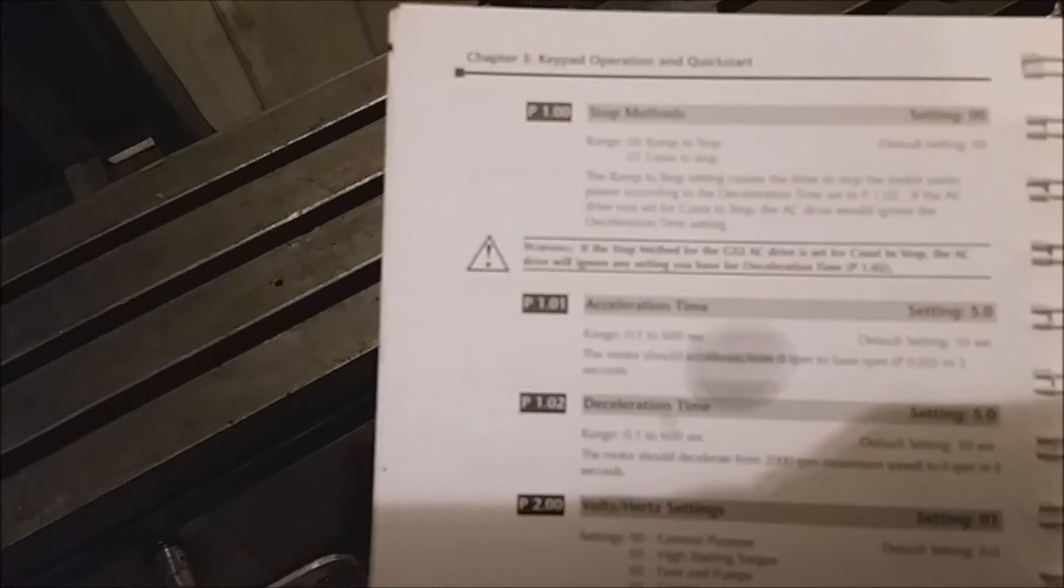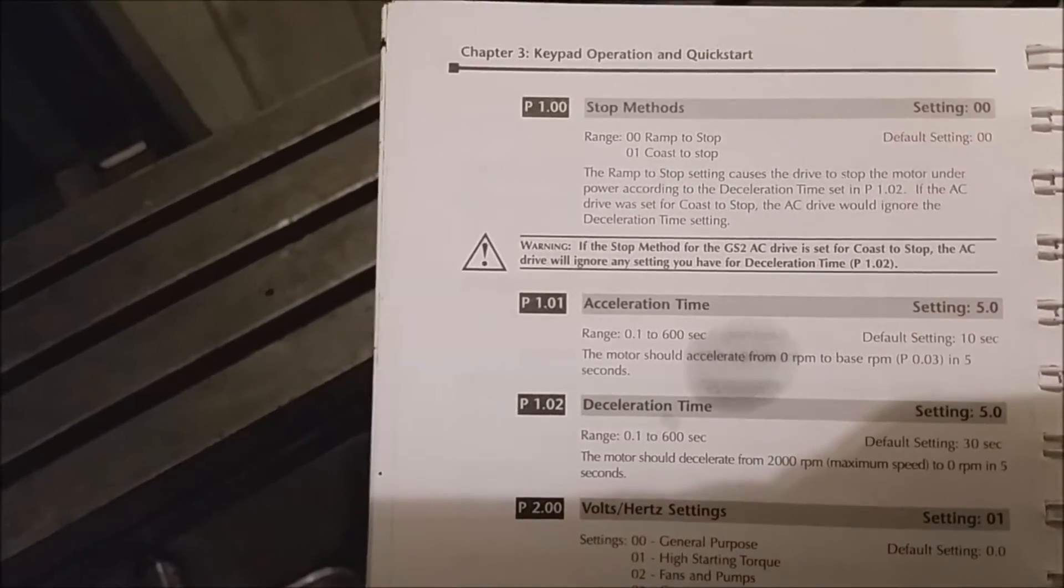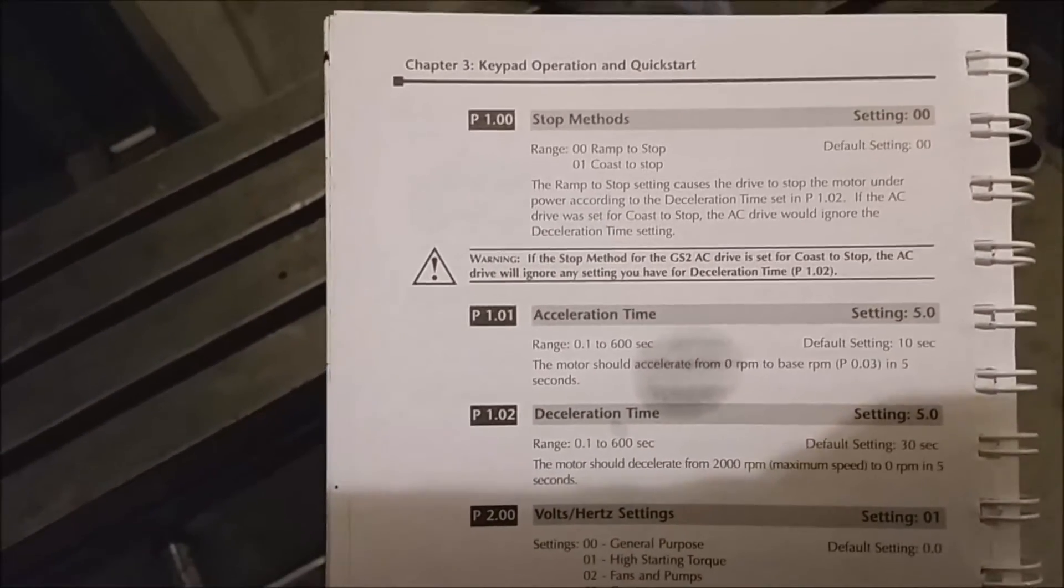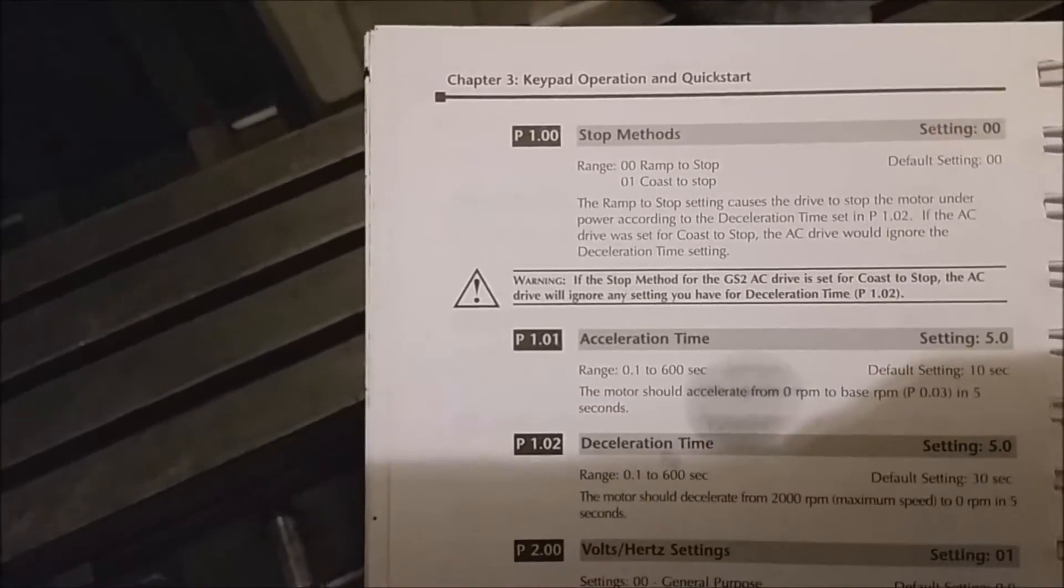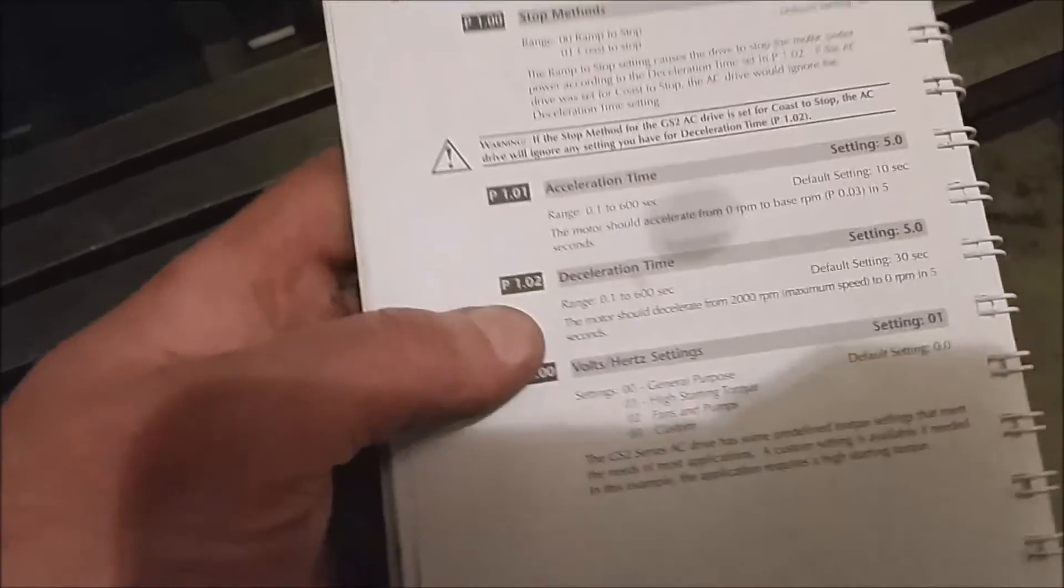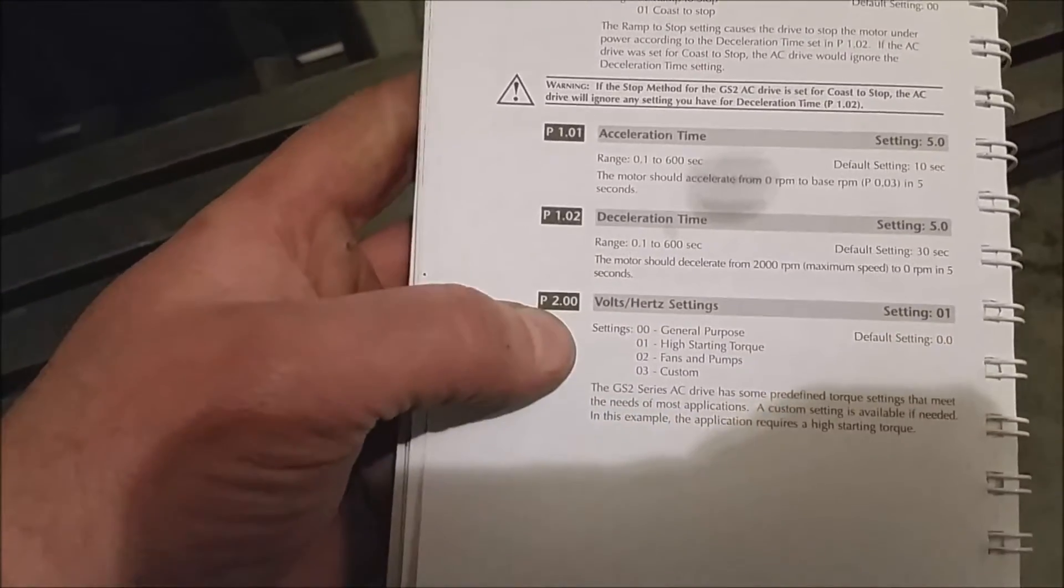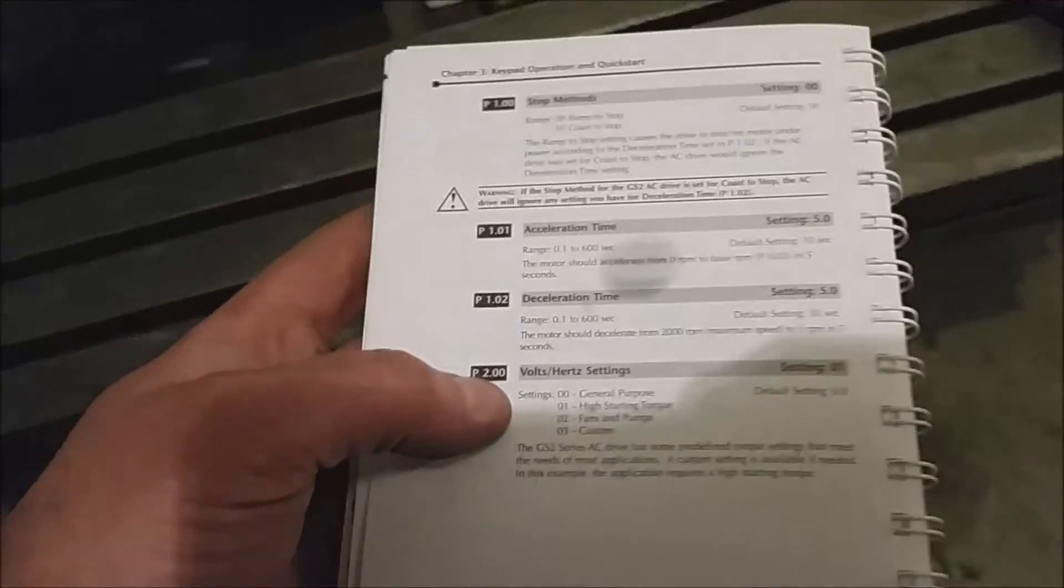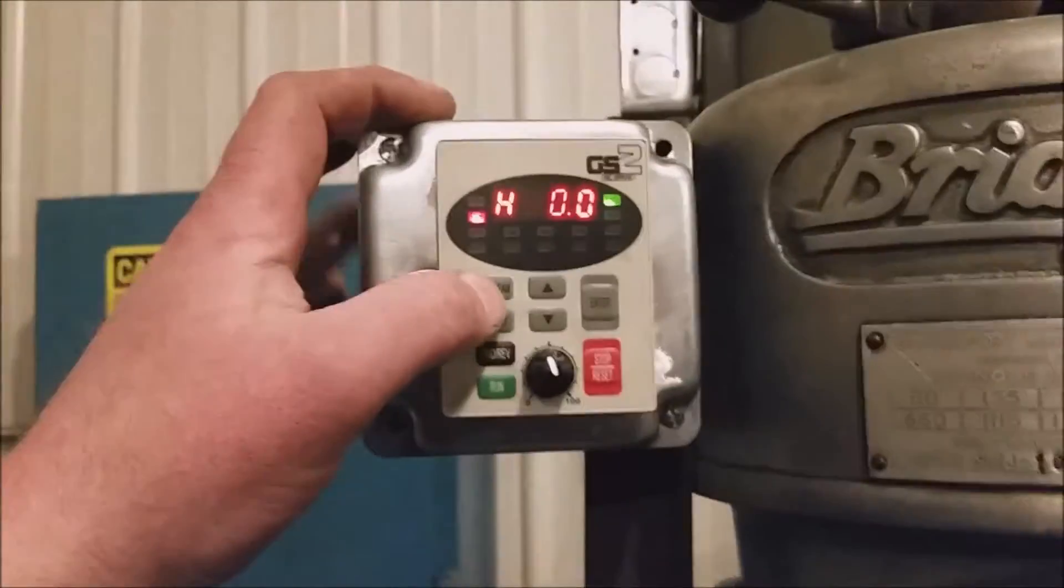You just walk down through those parameters. Then there's these parameters that you can set, like how you want it to stop. If you want it to stop by ramping to a stop, it can actually stop faster, especially if you have that braking resistor in there. Your acceleration time, your decel time, your volts per hertz setting, depending on what kind of torque requirements you have.